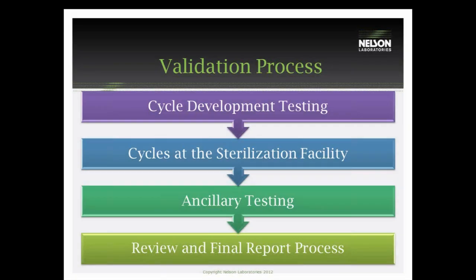This graph shows a little bit of how that process works in the chamber. For the validation process, we will typically do cycle development testing, which will evaluate the device as well as process challenge devices chosen for the validation process. That is followed by half and full cycles at the sterilization facility, all the ancillary testing, and the review and final report process. This process can take anywhere from four to five months.